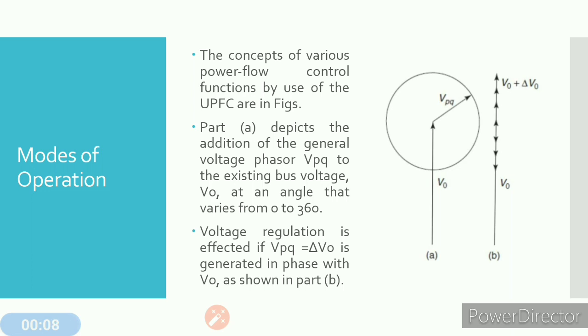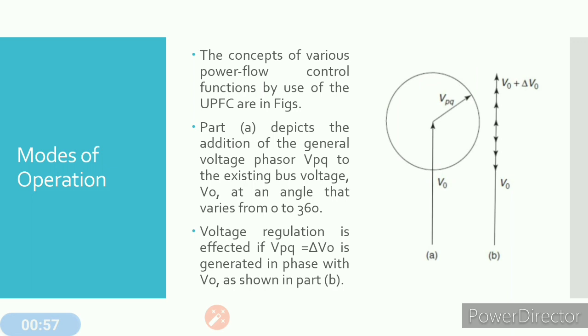The injected voltage can be varied in magnitude as well as in phase angle. Figure A shows how the voltage Vpq is injected to the existing bus voltage V0 at an angle that varies from 0 to 360 degrees. If the voltage is injected at the initial point, the phase angle of Vpq is 0 degrees, and it can be changed from 0 to 360 degrees as shown in the phasor diagram.